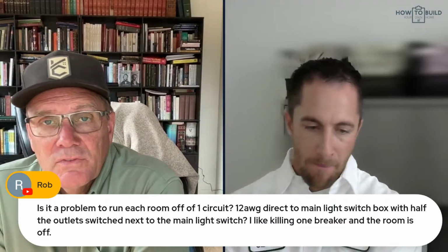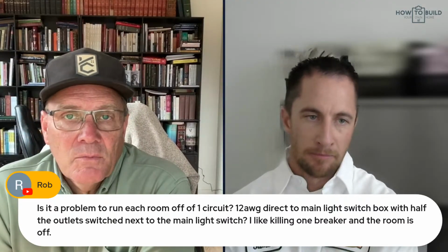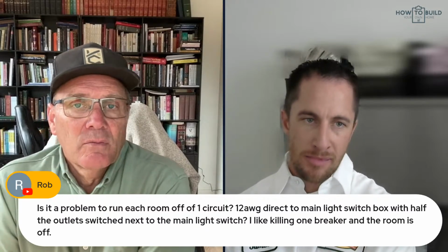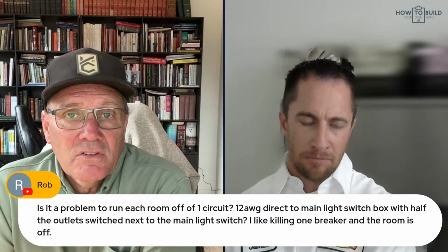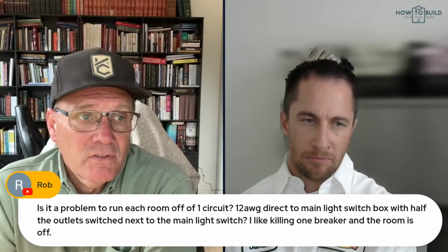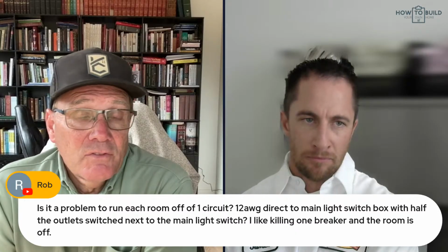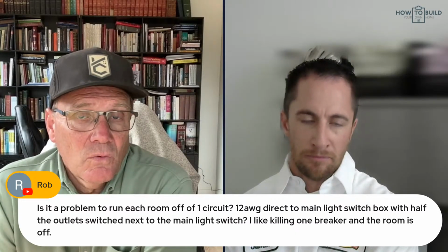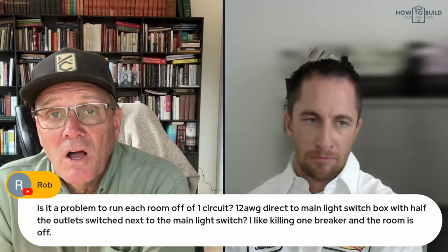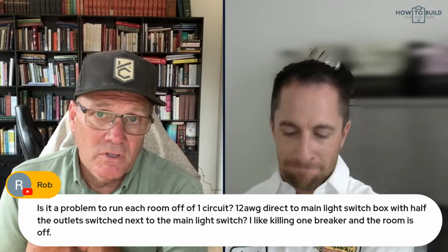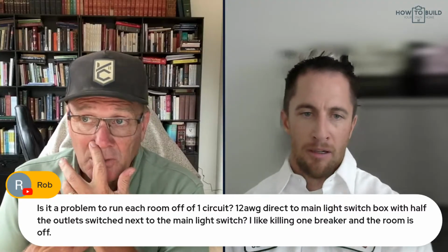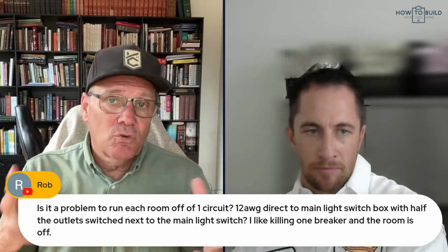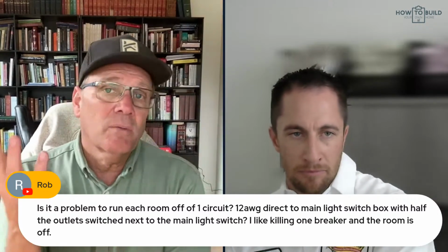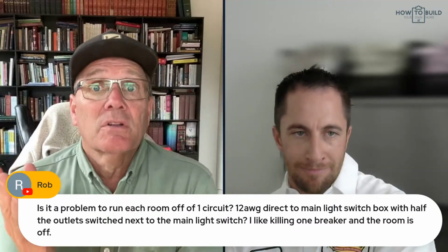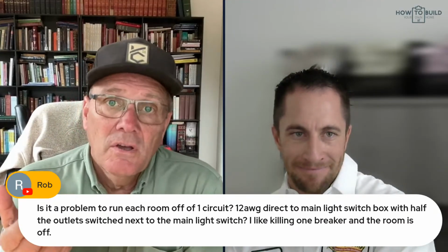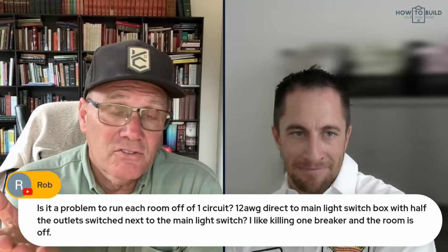I do have direct 12-2, which is really a 20 amp circuit. I call them DD, dishwasher and disposal, and one to a bathroom. I don't like to daisy chain too many outlets on a 12-2 line. For example, if you have 2 or 3 outdoor plugs, you can daisy chain all those on one 20 amp circuit. But when it comes to a garage, I personally love 2 20 amp circuits. Agreed, because I run a lot of power equipment and I'm charging stuff at the same time. Most homes built these days have one 20 amp circuit, and really cheap homes, and those in the past, you could find one 15 amp circuit, and that's just not enough at all.